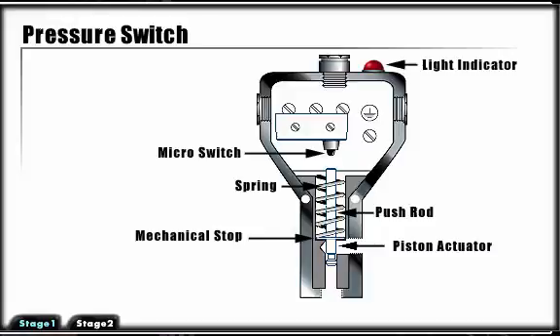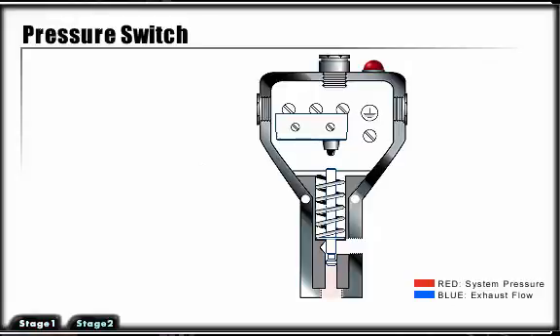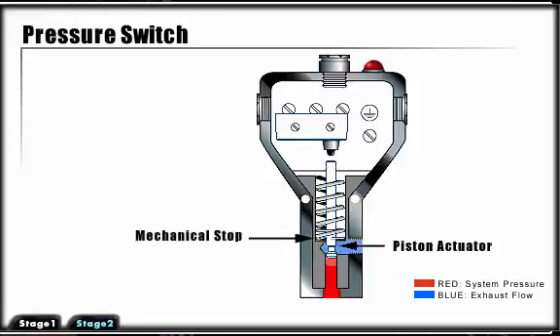External lights are often used to indicate that the switch has been activated. When pressure builds in the system, it enters the device applying force to the piston actuator. This energy is transferred to the mechanical stop, compressing the spring, driving the push rod up until it activates the micro switch. Pressure switches are used to open or close an electrical circuit when a predetermined pressure has been reached.